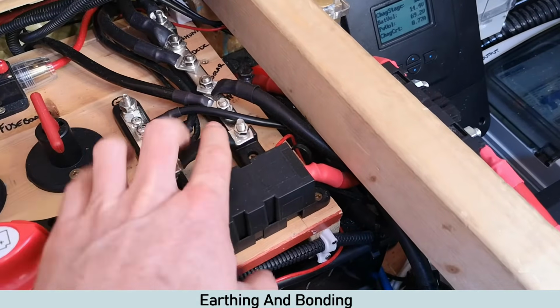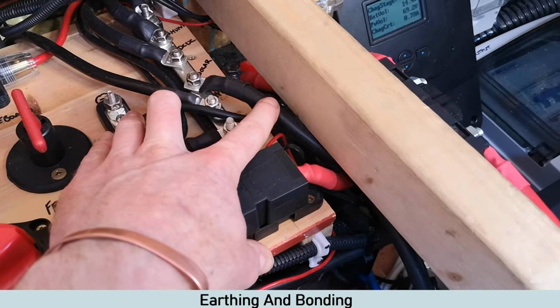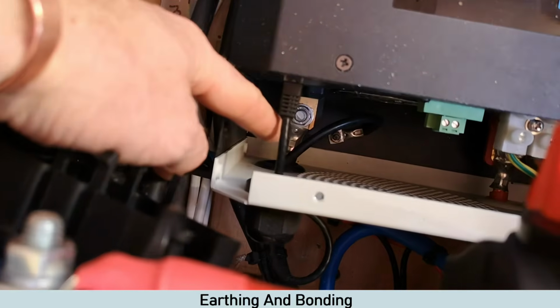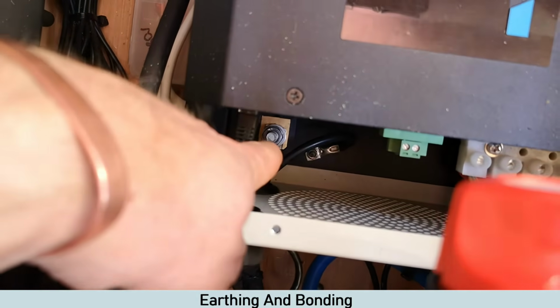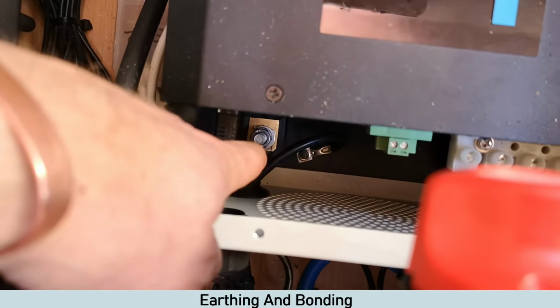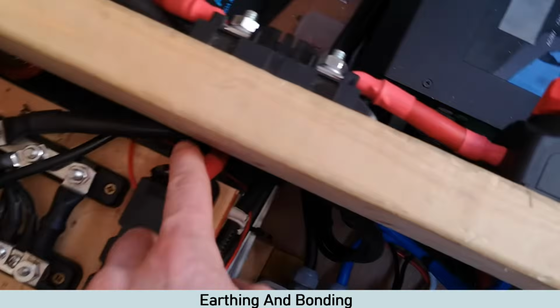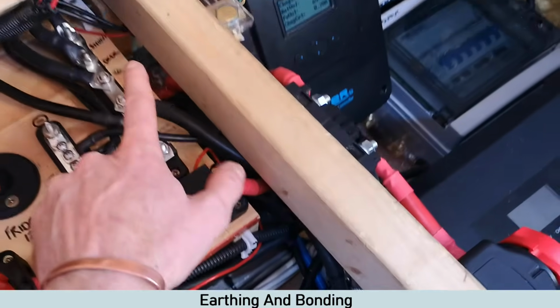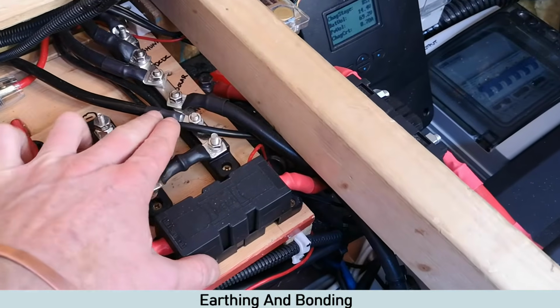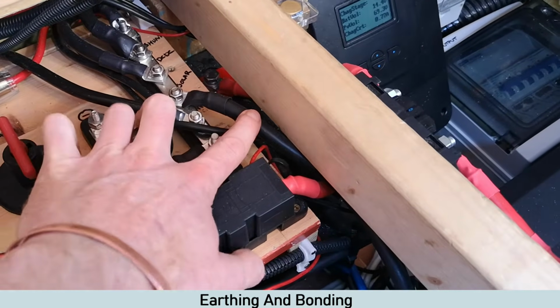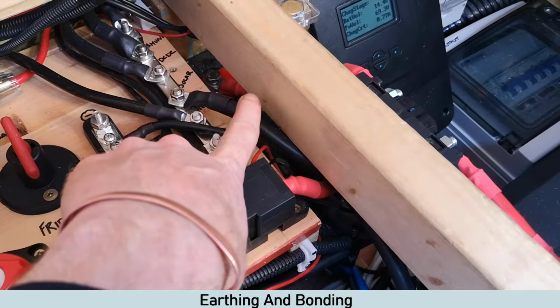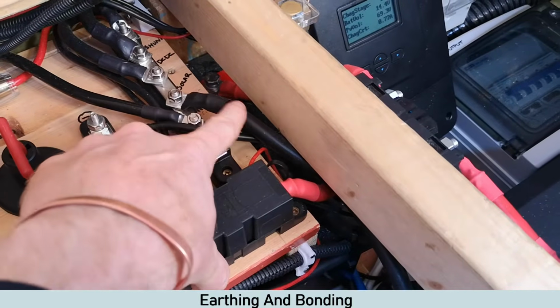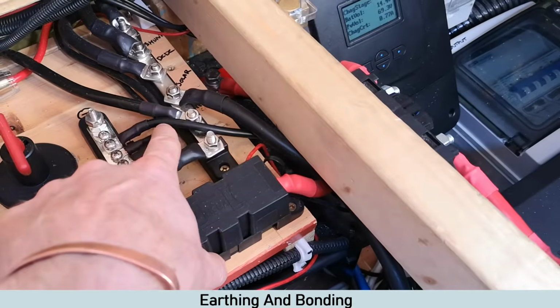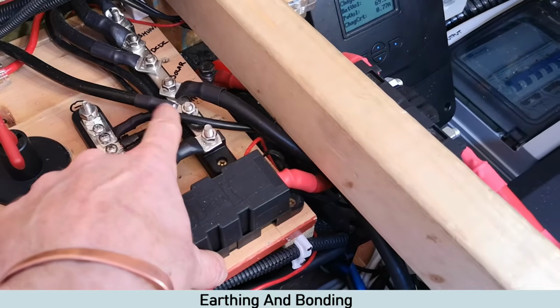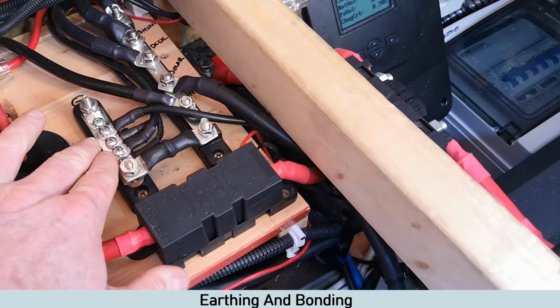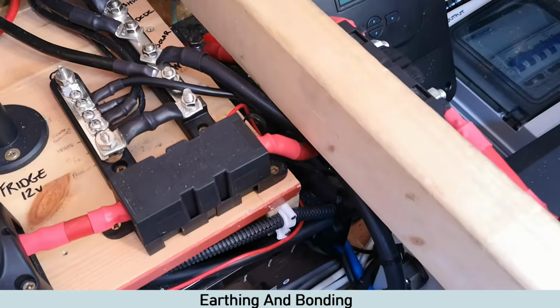Now we have been asked before whether you can combine this ground with this cable. So basically, rather than running the cable all the way to the busbars, you go straight from there onto the negative point there. You can, obviously, and it will be grounded because it goes the same route, this cable does. However, it's kind of frowned upon. You shouldn't really mix a bonding cable or a grounding cable with a supply cable. So if you ever lose the supply for any reason, this comes off or whatever, it's likely not going to happen, but you also lose your grounding point. So it's quite important to keep these things separate. So if there's ever an issue, you've still got one of these in place.